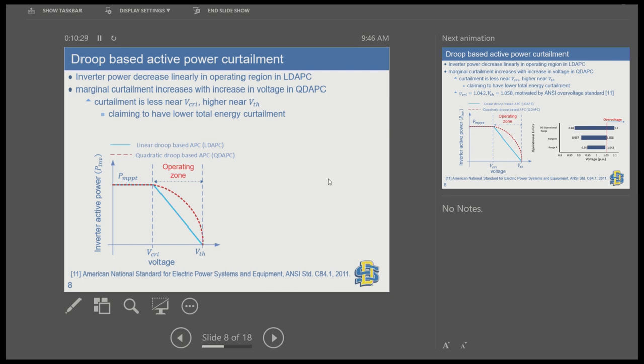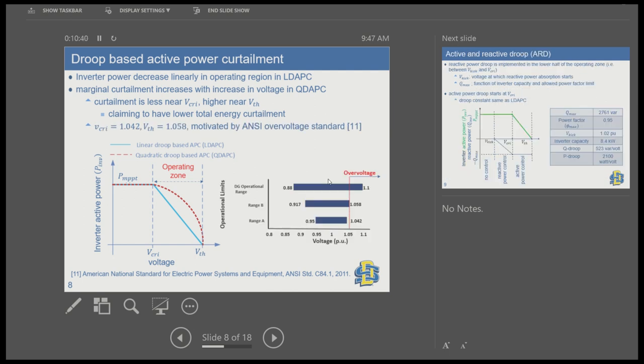In the quadratic approach, higher curtailment occurs at higher voltage but lower curtailment at lower voltage, which has a special benefit in reducing energy curtailment. For the critical and threshold voltage values, we use the ANSI standard, which defines range A for normal operations and range B as the critical range. We use 1.042 per unit as V-critical and 1.058 as the threshold voltage.